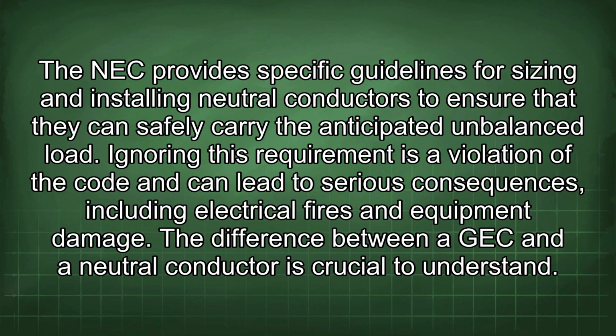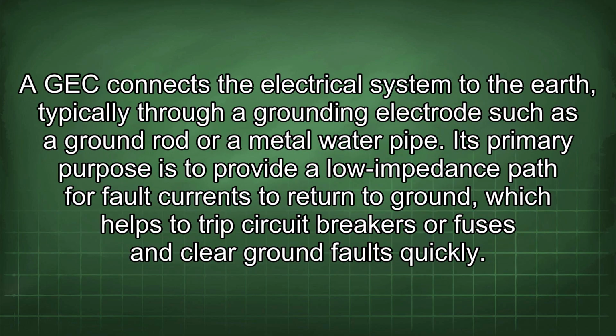and equipment damage. The difference between a GEC and a neutral conductor is crucial to understand. A GEC connects the electrical system to the earth, typically through a grounding electrode such as a ground rod or a metal water pipe. Its primary purpose is to provide a low impedance path for fault currents to return to ground, which helps to trip circuit breakers or fuses and clear ground faults quickly.